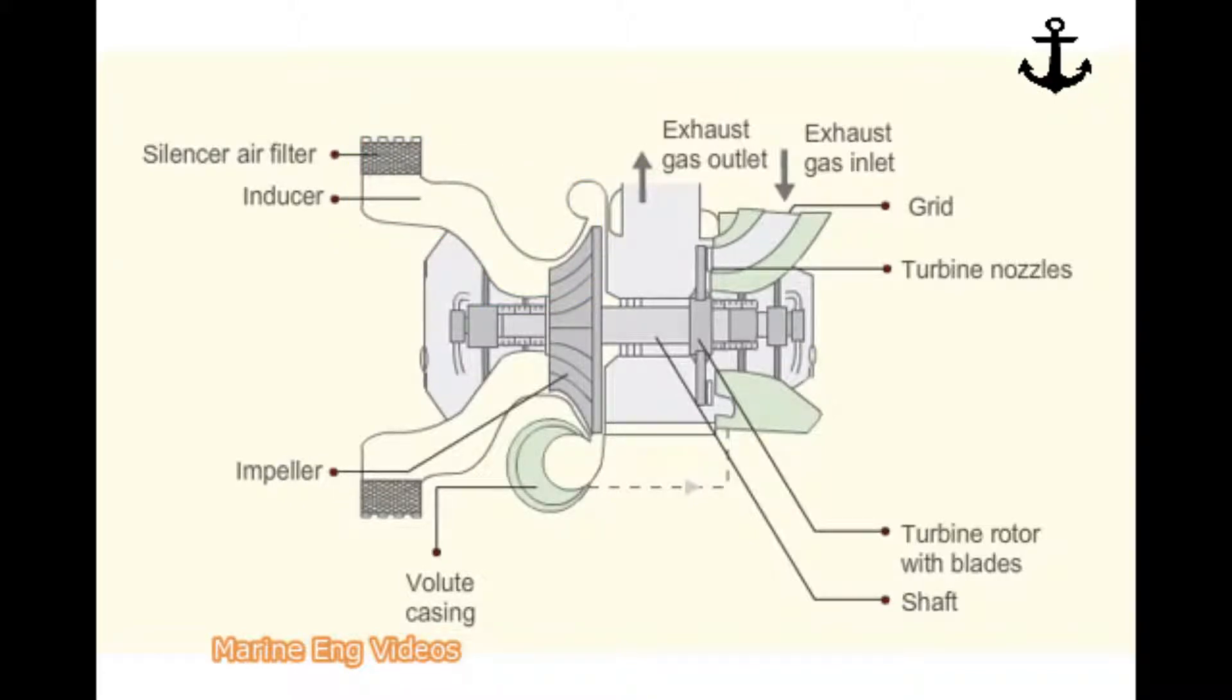Impeller discharges the air radially through diffuser and volute casing to the air cooler. The diffuser and volute casing have divergent shape which reduce the speed of air passing through them. This reduction in speed converts kinetic energy into pressure energy.